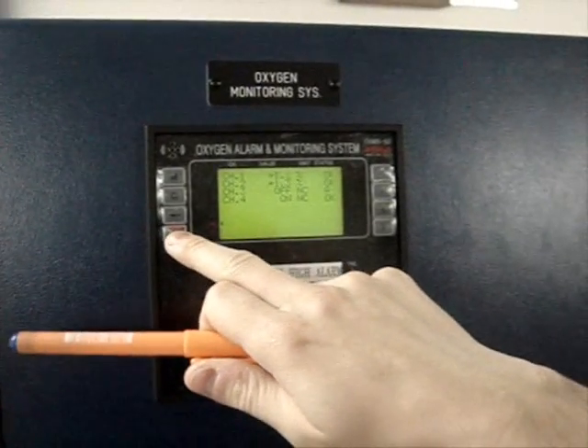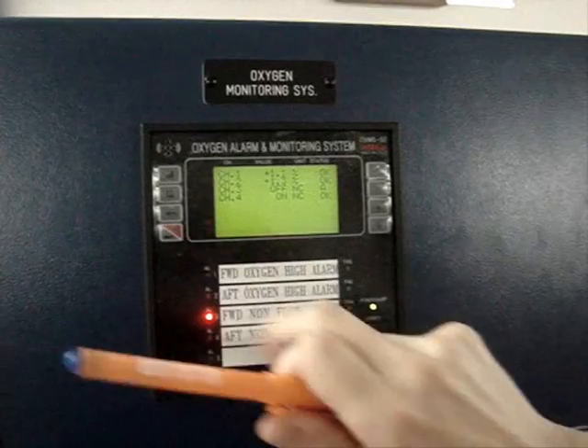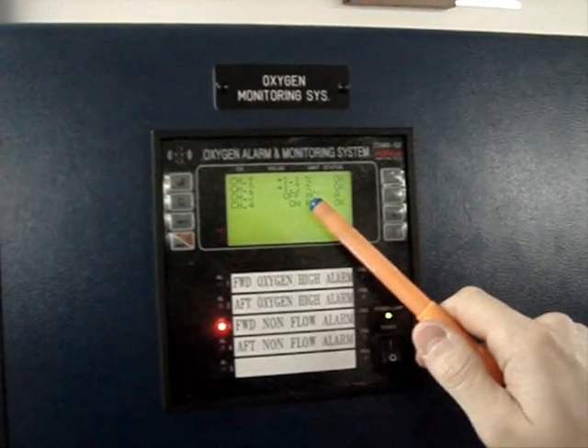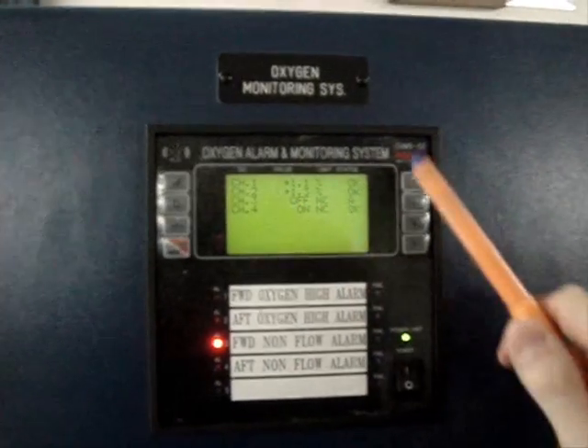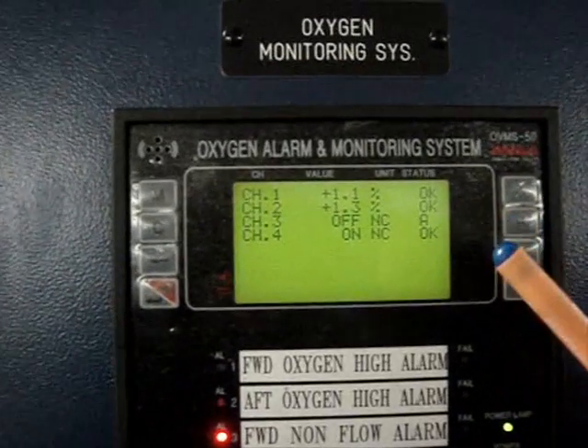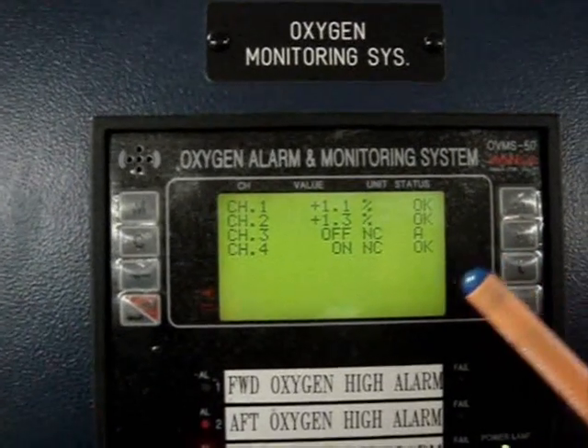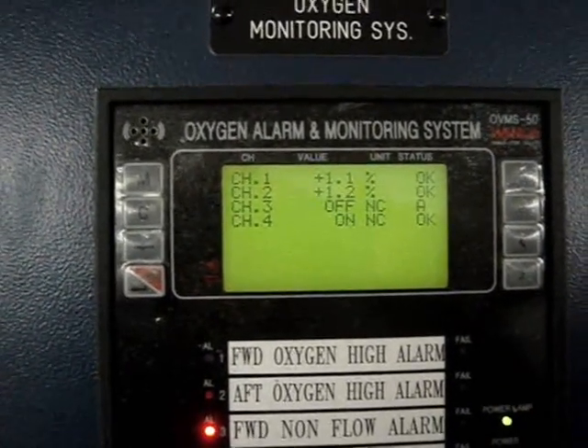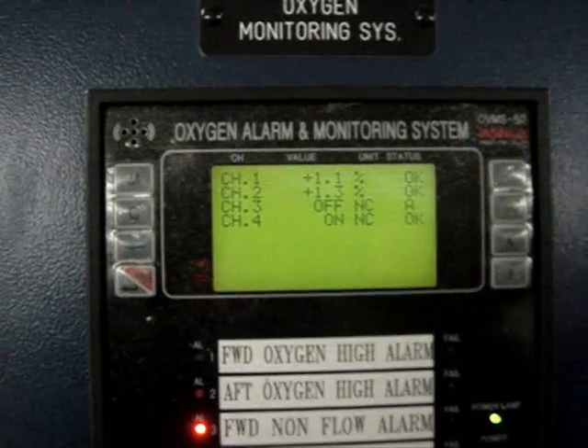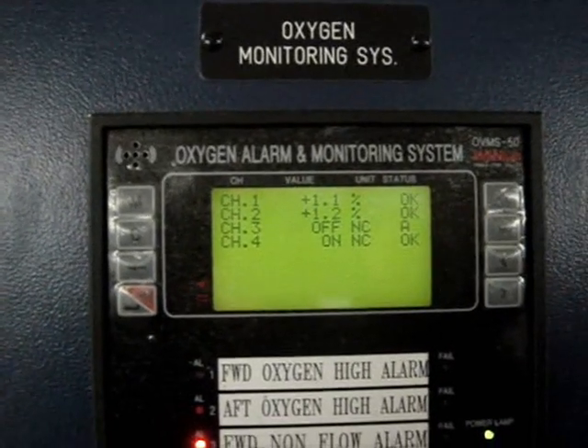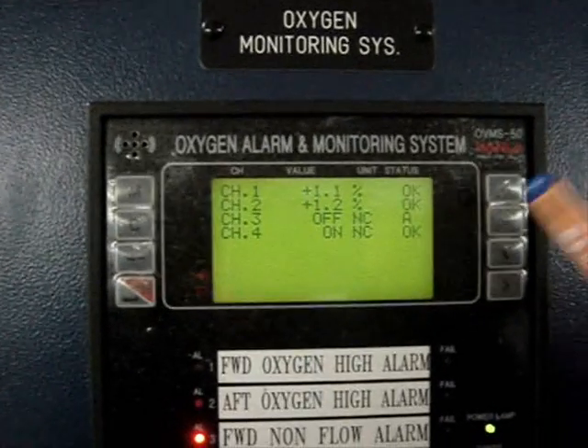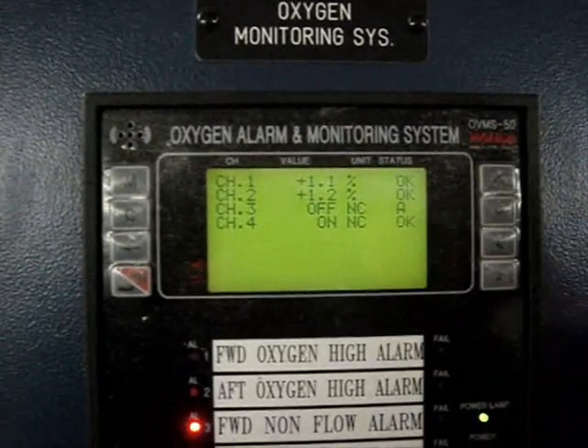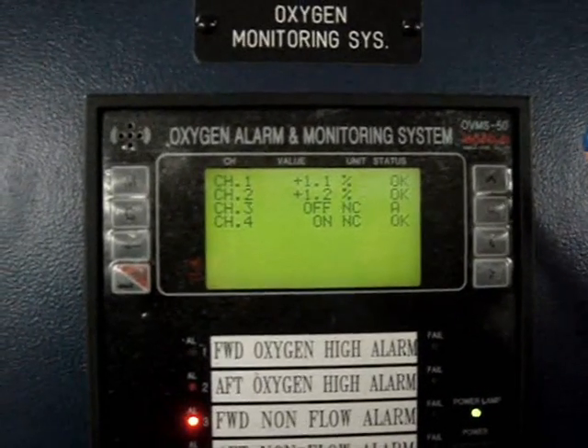We can silence the alarms by pushing the sound-off button. There is one alarm showing, which is a non-flow alarm because the sampling point is disconnected. Channel one and two are showing the oxygen content on the line.